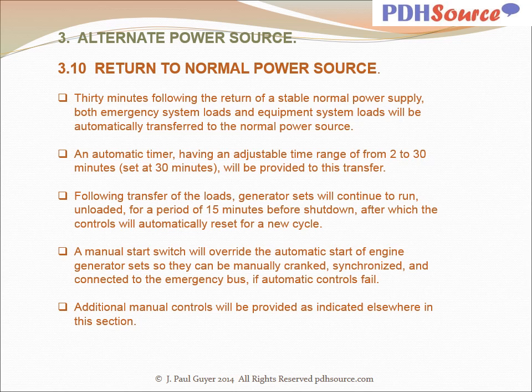30 minutes following the return of a stable, normal power supply, both emergency system loads and equipment system loads will be automatically transferred to the normal power source. An automatic timer having an adjustable time range of from 2 to 30 minutes, which will be set at 30 minutes, will be provided for this transfer. Following transfer of the loads, generator sets will continue to run unloaded for a period of 15 minutes before shutdown, after which the controls will automatically reset for a new cycle.